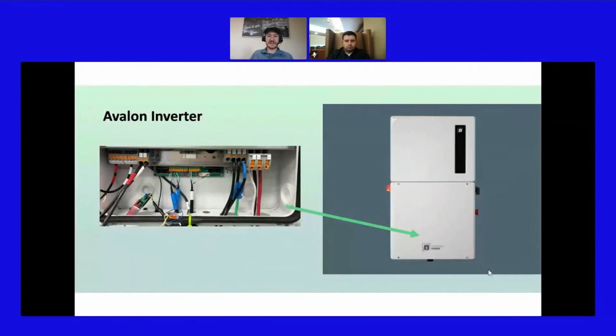Now it can be AC coupled, but we'll talk about AC coupling when we talk about the smart energy panel. But most of your savings with the Avalon system are going to come in a DC coupled system, because this inverter acts as the battery inverter as well as the PV inverter, and it gives you added efficiency so that you don't have to add additional panels to account for the loss of efficiency you typically get with AC coupled systems.